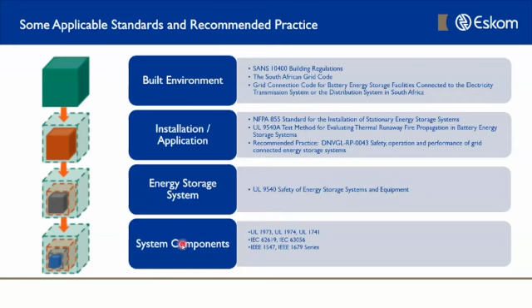One of our main standards for energy storage system fire prevention was NFPA 855, the National Fire Protection Association standard. Some of the things they ask you to consider when building these systems: are they indoor or outdoor? This is very important, especially in terms of the size of the system. In actual fact, we can't do too big a size indoor because of the risk - because of off-gassing, because of explosion risk.